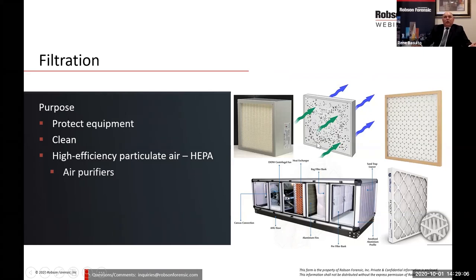The original purpose of the filters inside an equipment was to protect the equipment itself. Remember, air has to go across a coil, either an evaporator coil or a heating coil, depending on what your system is doing, whether you're heating or cooling. But those tend to be fairly tight fins. So if you start getting dust and pollen and hair and all sorts of stuff drawn into the air, you're going to end up clogging those coils.